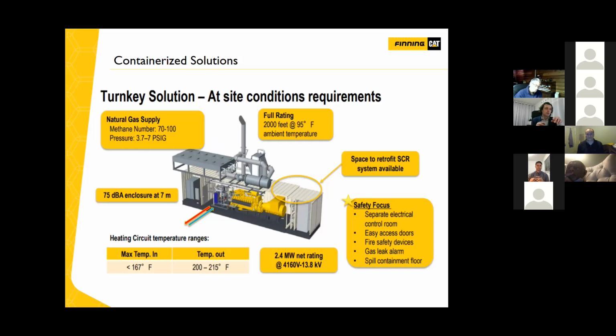Well, I could maybe take that. Most of Caterpillar's natural gas gensets are low pressure gensets, which does help. It's not a high pressure system like some others that make it a classified building. With this, we can actually treat the genset like a standard appliance. There is a final regulator on the genset which makes it a zero pressure regulator, but incoming to the gas train the pressure is 3 to 7 psi across most of Caterpillar gensets.